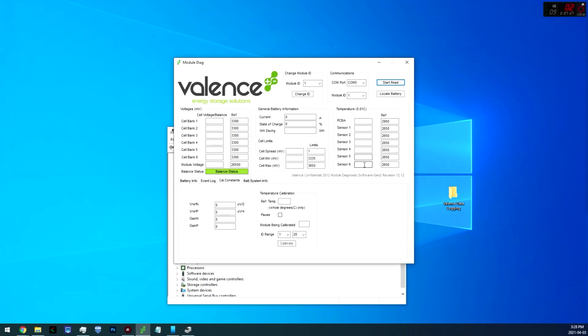So that's the next thing. If you got a battery secondhand and don't know what the module ID is, because maybe it came out of a big bank, once you have the correct COM port, just click Locate Battery. This battery is a U1-12 XP revision 2 with an ID of number 4, so I just have to go to module ID 4 and start read.